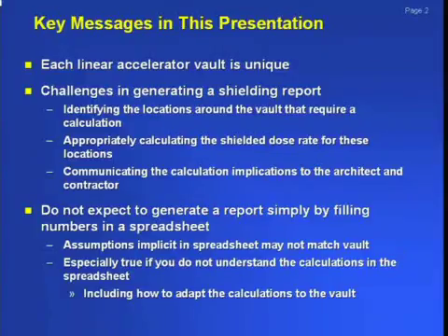You need to make sure you are appropriately calculating the shielded dose rate for these locations. And one of the larger challenges that I've run into, at least, is correctly communicating the calculation implications to the architect and the contractor. We can give very high-level reports, but if your architect and particularly your contractor do not understand how you want the vault built, you will create lots of problems. So that is probably my number one take-home.